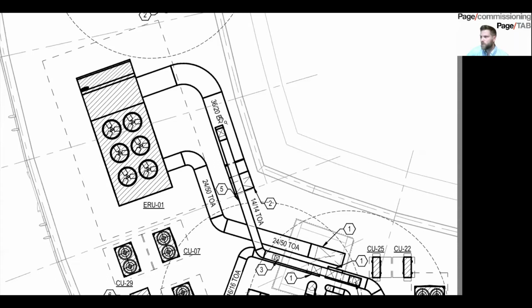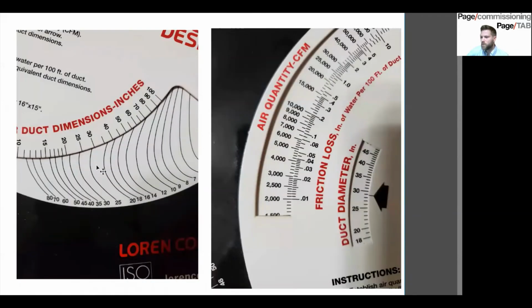So then let's just double check these numbers. So a 36x20. What kind of flow can a 36x20 do at that 0.08 friction loss? You'll start to line it up, and you do that 36x20, which is, you can go either way. So I'm just going to pick this one, which is 35. You're just going to go like a little notch ahead, because it's just barely past that. You have 5 points in between here, and you're just going to go barely past, draw this line all the way up here, and you're practically at 20, right?